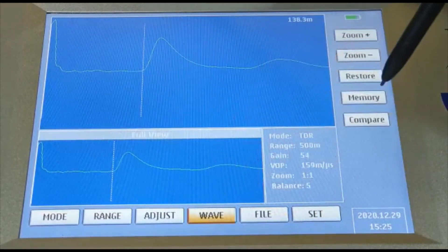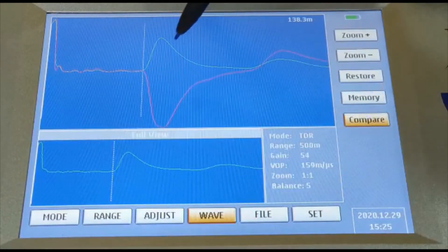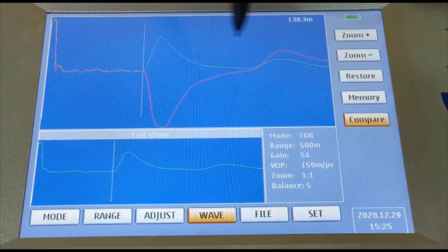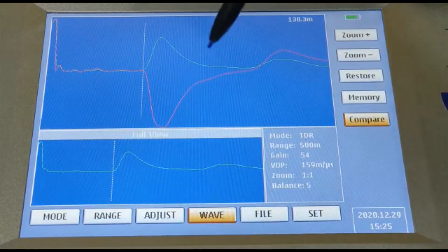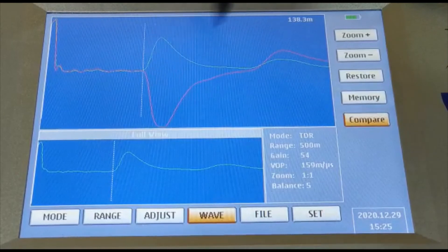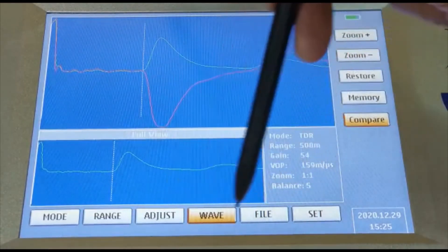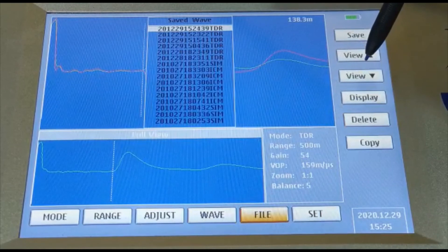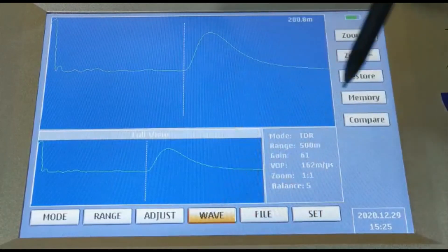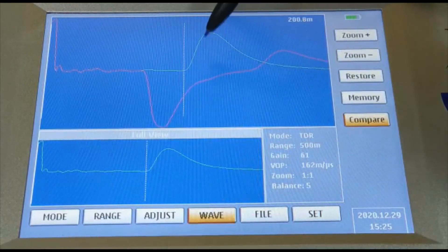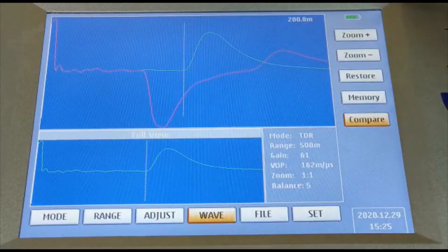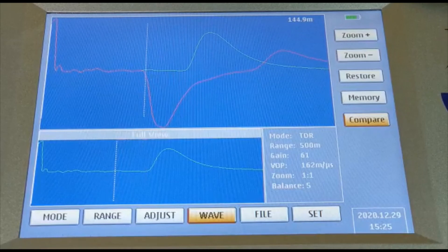If you want to compare files, go to compare and see what's happening. You can see two different files which give information about the fault distance, comparing what's happening in the cable — this is an open circuit fault and a short circuit fault. Go to file, select another file, display it, then go to wave and compare. You can see that the end of the line is at 200 meters open circuit and the fault has been created at 138 meters.